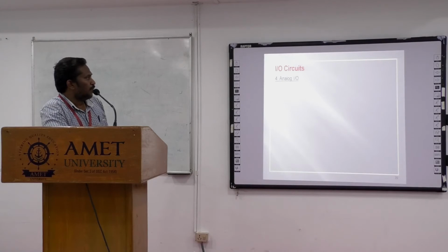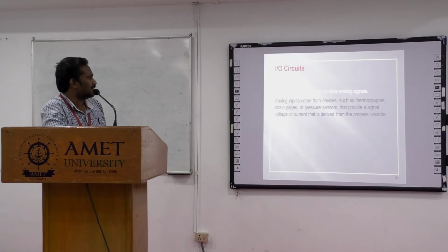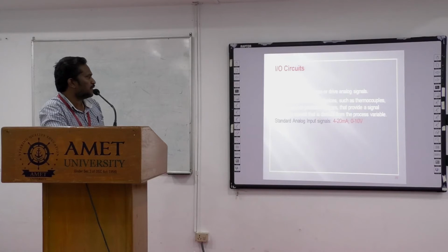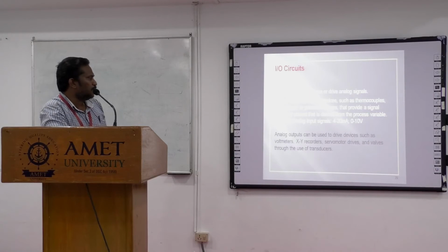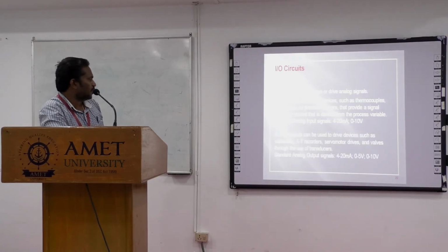The fourth one is analog input output modules. Circuits of this type sense or drive analog signals. Analog inputs come from devices such as thermocouples, strain gauges or pressure sensors that provide a signal, voltage or current, that is derived from the process variable. Standard analog input signals are 4 to 20 milliampere or 0 to 10 volt. The analog outputs can be used to drive devices such as voltmeters, XY recorders, servo motor drives and valves through the use of transducers. Standard analog output signals are 4 to 20 milliampere, 0 to 5 volt, 0 to 10 volt.